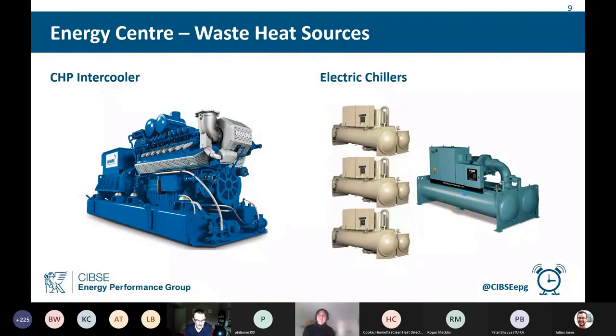It's powered by CHP, which has an intercooler with waste heat that currently just goes to atmosphere. Similarly, the electric chillers that produce the cold water emit waste heat. So we are going to capture that waste heat and use it to heat up the return water before it goes to the boreholes, so that we can utilise the waste heat.